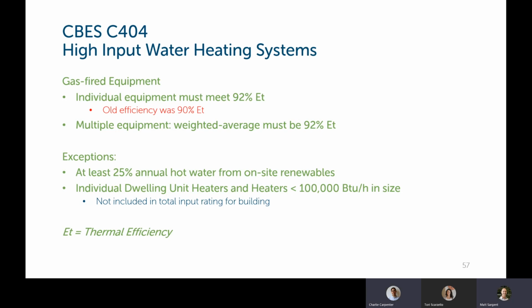For high input water heating systems, pretty big systems in commercial buildings, for gas fired equipment, the individual equipment thermal efficiency has been increased from 90 up to 92. And if you've got multiple pieces of equipment all serving the hot water demands of a building, the weighted average of the capacity of all those units combined must be 92% efficient. So you could have some units lower, some higher, but based on the capacity, averaged altogether must be also equal to 92%. There's some exceptions to this.